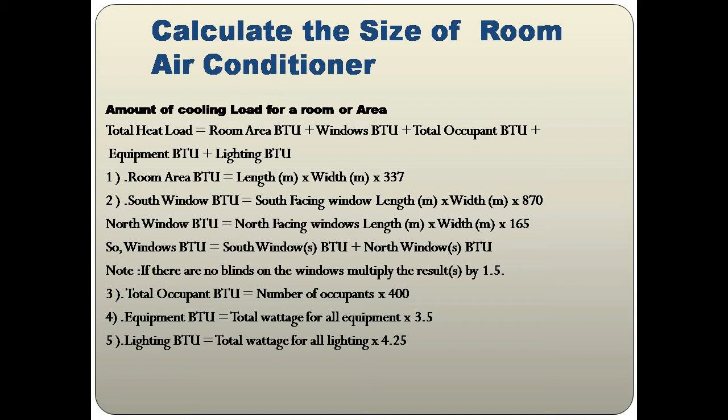For Windows BTU, there are two types: south-facing and north-facing windows, each with a different calculation. For a south-facing window: length × width × 870. For a north-facing window: length × width × 165. Total Windows BTU = South Windows BTU + North Windows BTU. If there are no blinds on the windows, multiply the total windows BTU by 1.5. If there is no window in your room, you can skip this step.